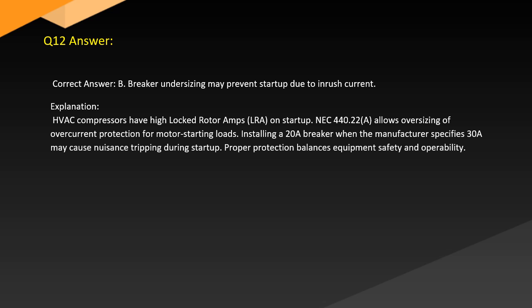Answer. Correct answer: B. Breaker undersizing may prevent startup due to inrush current. Explanation. HVAC compressors have high locked rotor amps, LRA, on startup. NEC 440.22(A) allows oversizing of overcurrent protection for motor starting loads. Installing a 20 breaker when the manufacturer specifies 30 may cause nuisance tripping during startup. Proper protection balances equipment safety and operability.